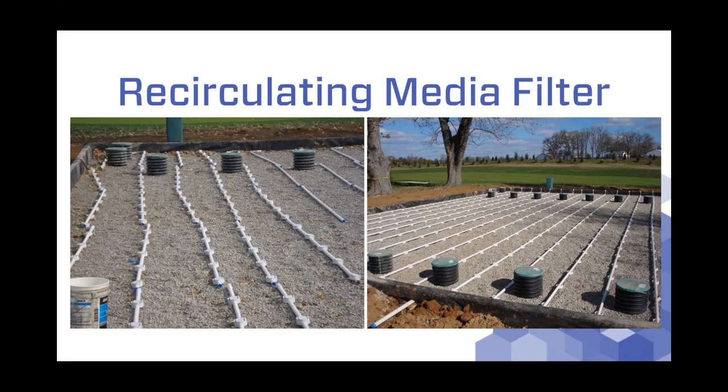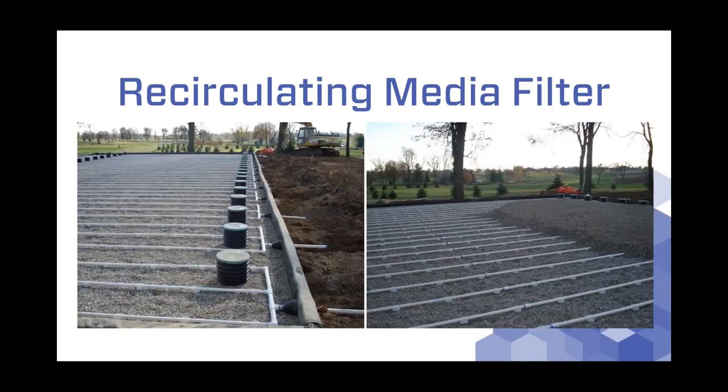You can see the zones more clearly here. In these gravel filters, we have a number of zones — you can see the manifold coming through the pipe boot, going out to another manifold with three laterals coming off it for zone one, then zone two, zone three, zone four, and so on. One of the main reasons we do this is because we're only dosing one zone at a time, which allows us to use a smaller pump. That helps keep the pump size and cost down.